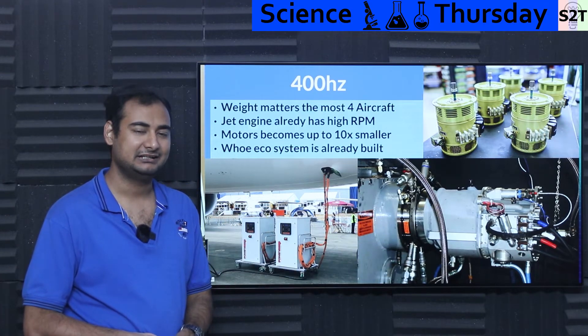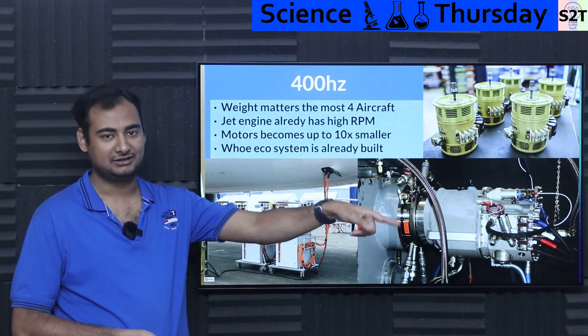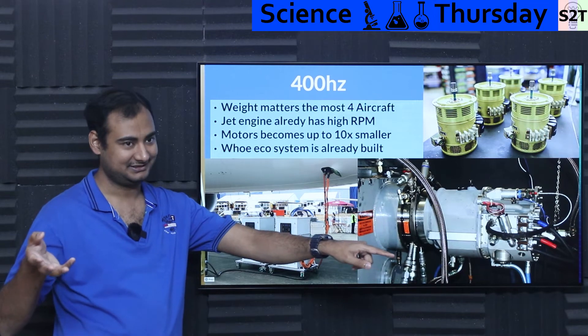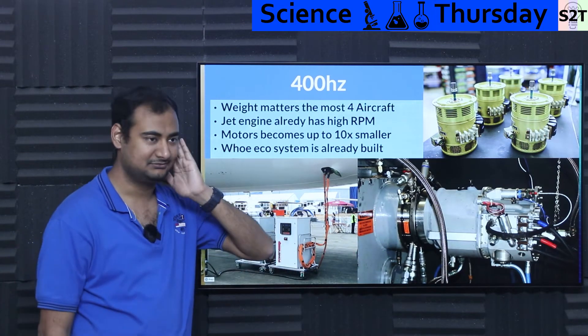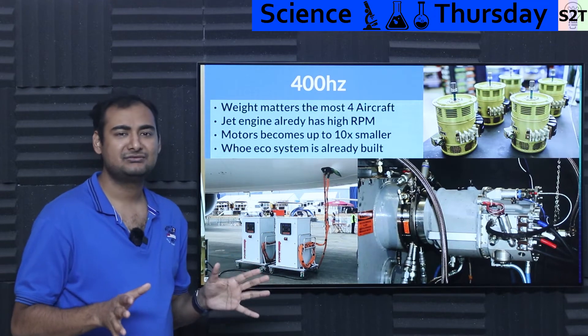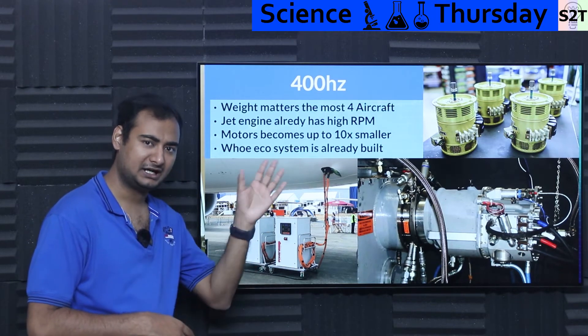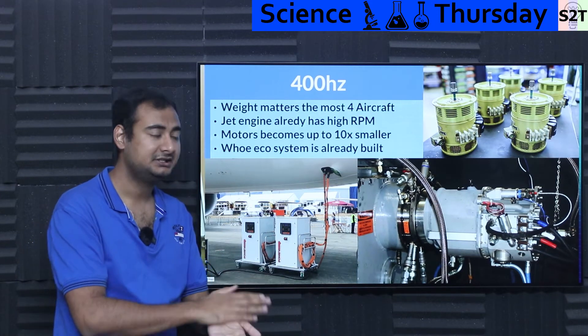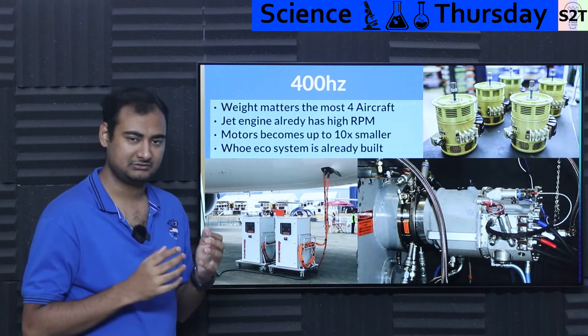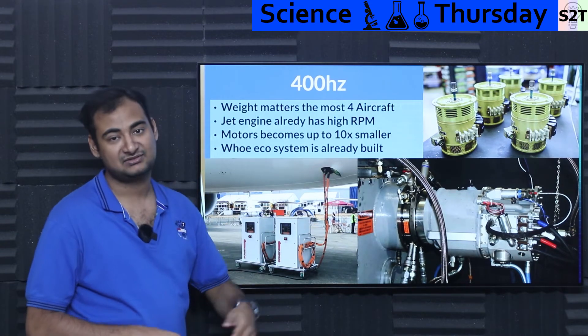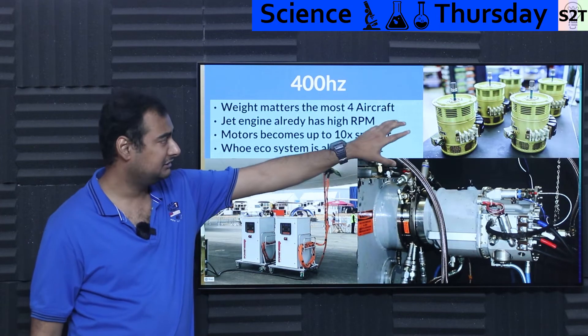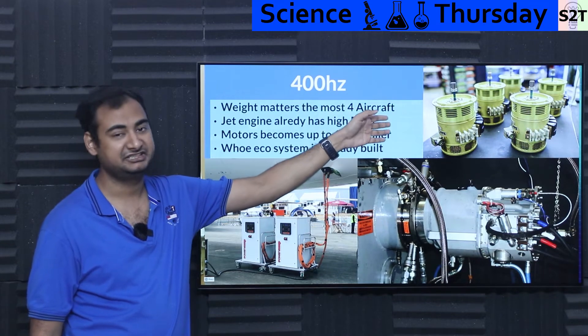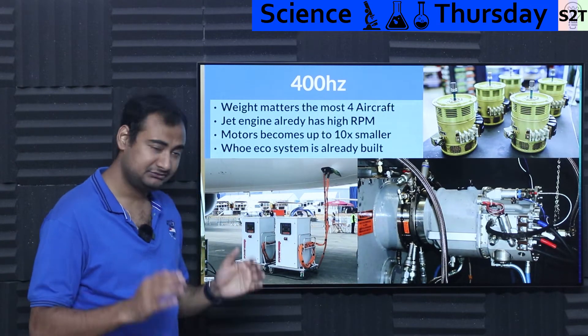Why only 400 and not 500? It's always a balancing act. If you go very high frequency, the skin effect and capacitance losses would make the aircraft wiring a hassle — for example the nose gear might not receive electrical power from a very high-frequency AC source. So 400 was a good compromise: not too high, not too low. Once engineering was sorted at 400 Hz, most engineering firms building equipment for it achieved 10x smaller sizes. Something meant for 50 or 60 Hz at 1 kilowatt — at 400 Hz it could be 10 kilowatt, or 50 kilowatt in the same form factor.